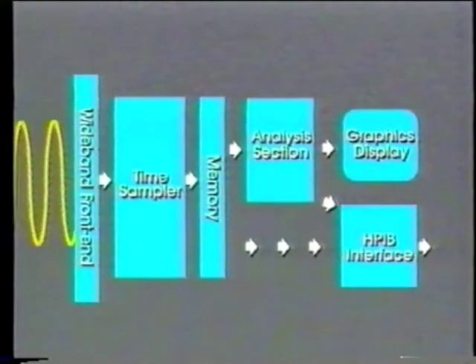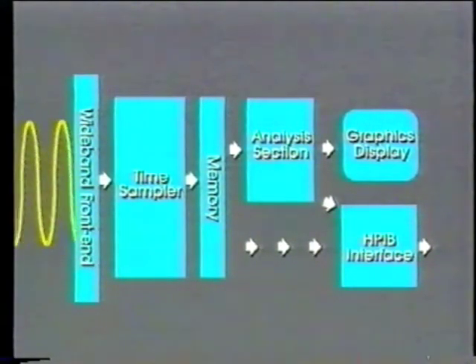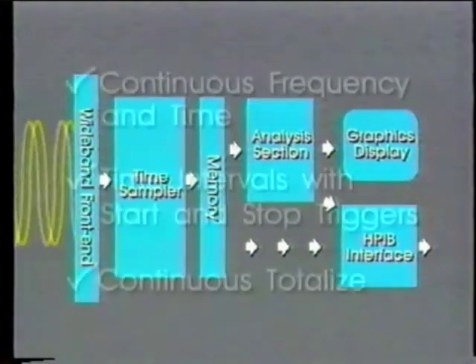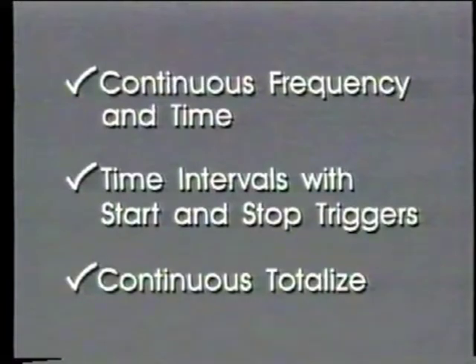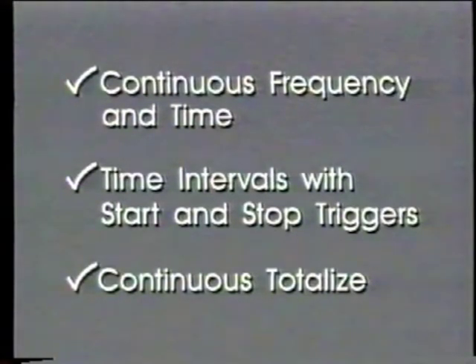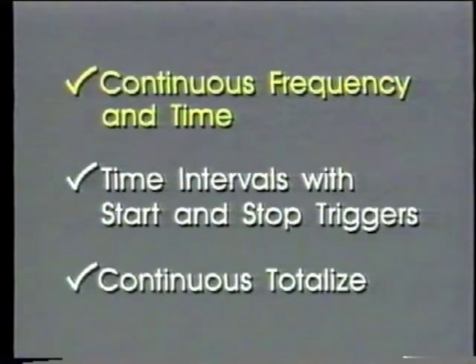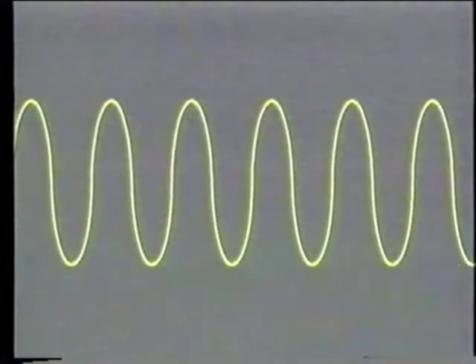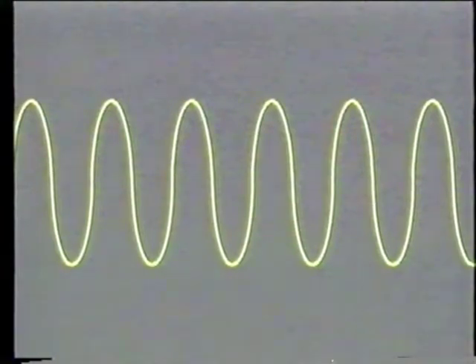Now that we've seen how the 5371A works in general, let's see what happens inside as we make three different types of measurements. To make a continuous frequency measurement, we count single trigger events — in this case zero crossings — and at user-defined intervals, tag them with time.